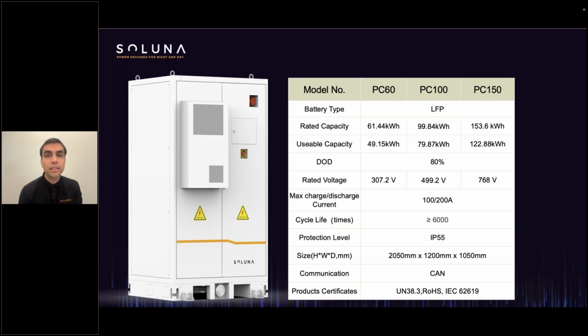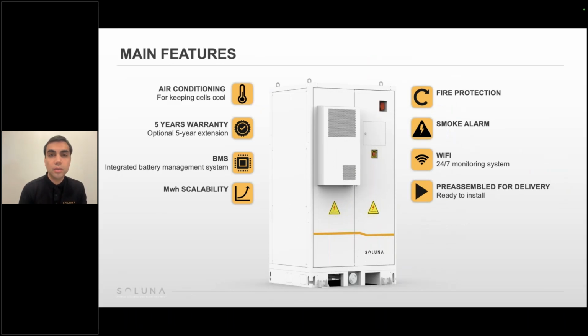The rated voltage for the PC60 is 307.2 volts. For the PC100 is 499.2 volts. For the PC150 is 768 volts. The maximum charge current is 100 amps and the maximum discharge current is 200 amps, with a life cycle of 6,000 and protection level IP55. The height of all these batteries is 2,050 millimeters, 1,200 millimeters in width, and 1,050 millimeters in depth. The communication is CAN, and we're working to get the UL 9540 certification with Solis on this one. So I believe it's in the works for this year.